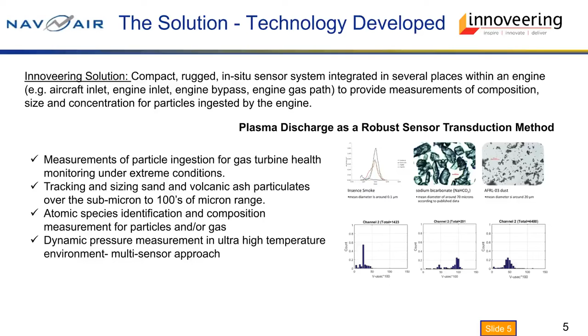In addition to enabling the measurement, the high-energy microplasma protects the sensing elements from fouling and maintains full probe function even under heavy particle loading conditions. Probes to date have accumulated hundreds of hours of use and continue to operate with no observable loss of function.